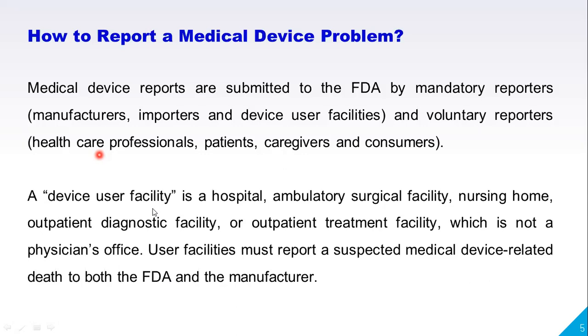Apart from the device user facilities, voluntary reporters are also able to submit or lodge a complaint. Voluntary reporters means healthcare professionals, patients, caregivers, and consumers. So any of them, if you are really facing any adverse event related to medical devices, you can lodge a complaint to the FDA and the manufacturer as per 21 CFR Part 803.